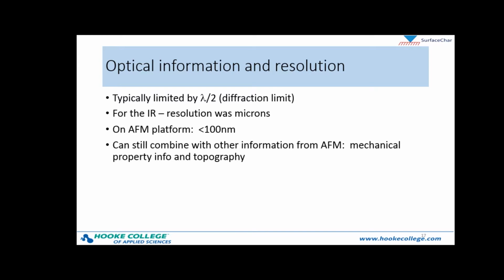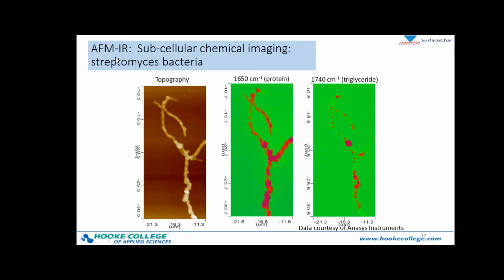And we can still combine this chemical information from the IR with the topography from the AFM, and then other channels that we've already explored today, such as mechanical properties. So here's an example of using AFM-IR to image bacteria. So here is a topography image of the bacteria. And then the IR image was zeroed in at particular peak, 1650 wave numbers, which corresponds to a protein, and then 1740 wave numbers, which corresponds to the triglyceride. And you could easily map the distribution of these two components in this bacteria and see where these individual components are with very high resolution.